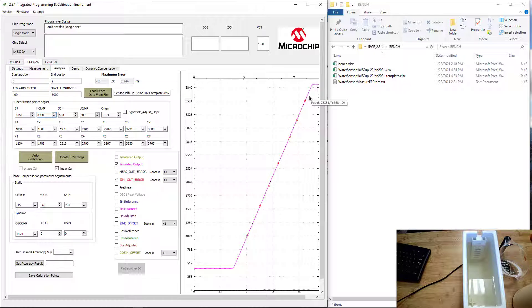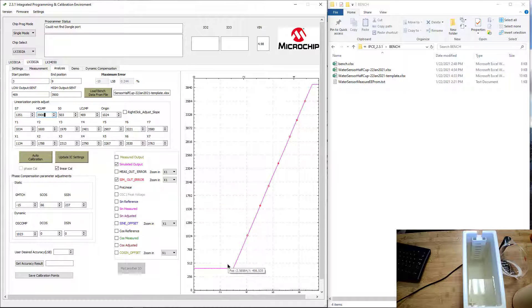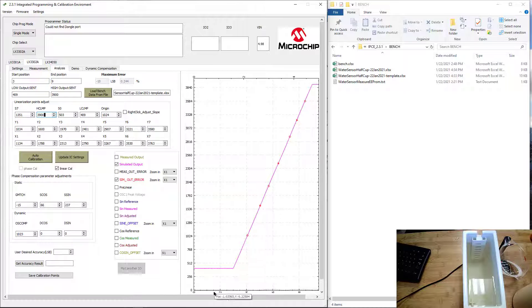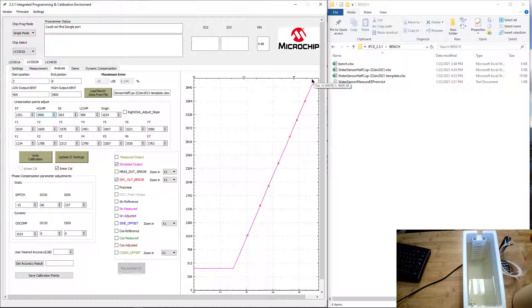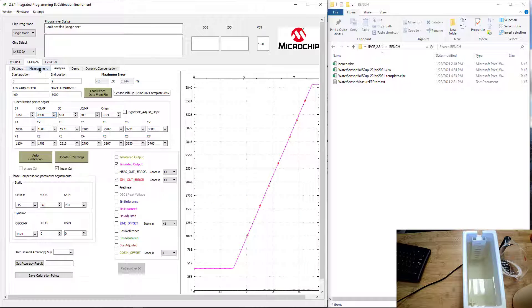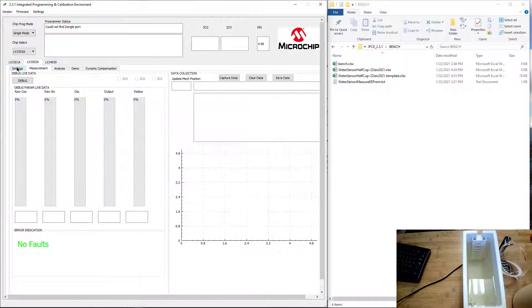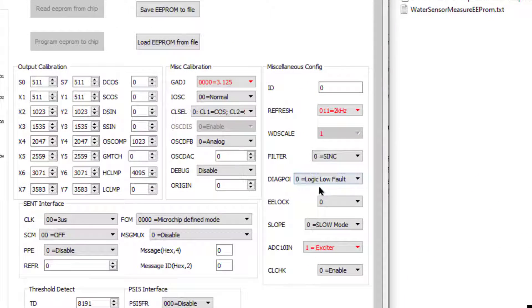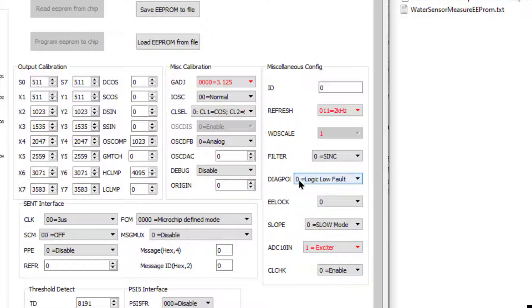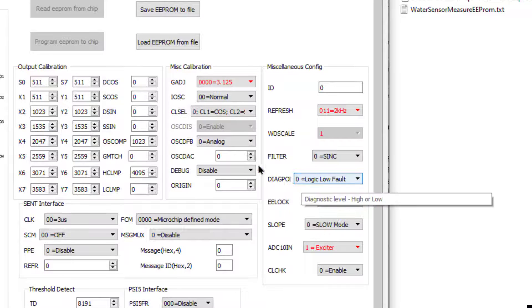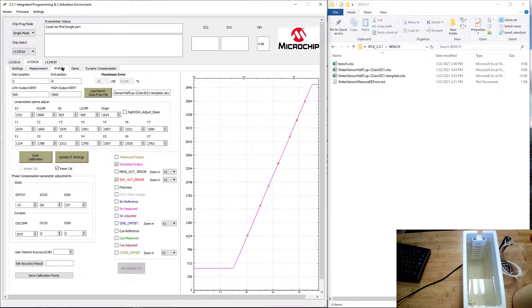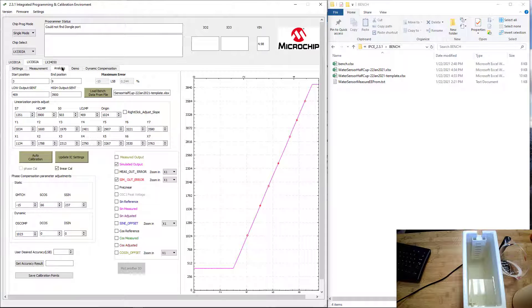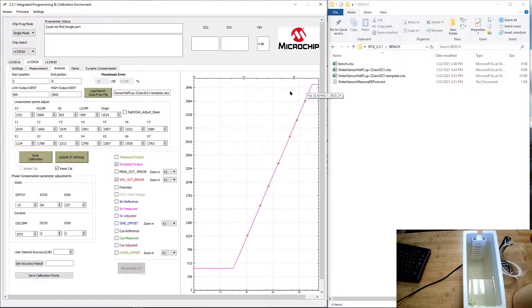This sets up an opportunity for fault indicator zones. So if the sensor goes into a fault mode, we will output either a zero or a high value, and those will indicate a fault. That information, I've mentioned in a previous video, is this diagnostic flag. Right now, this sensor is set so that when a fault occurs, it would be zero. In a future video, we'll talk about the types of faults you can detect with our sensor. We're ready, we're set here. It's been calibrated.